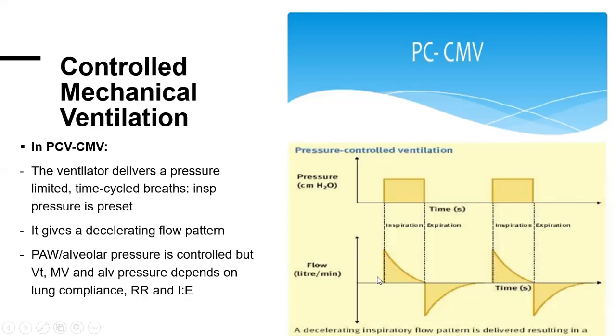But look at it here. If you look at the flow pattern on the right side, you'll see that it gives a decelerating flow pattern. And this is characteristic of pressure controlled ventilation.